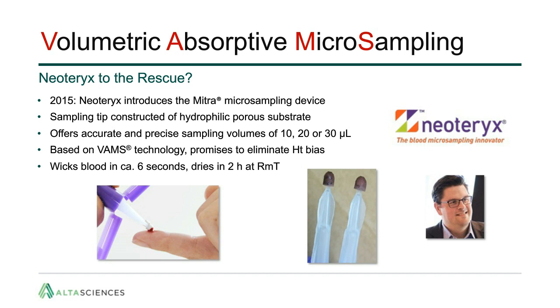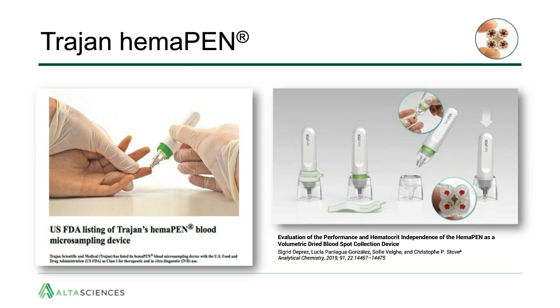Another volumetric approach is the Trajan hemaPEN, which received FDA approval as a Class 1 device on July 2nd for therapeutic and in vitro diagnostic use. It collects blood via four integrated 2.74 microliter microcapillaries, depositing blood on pre-cut paper discs when the cap is replaced. In our experience it was straightforward to implement, with the advantage of quadruplicate sampling for biobanking whilst eliminating tampering risk and maintaining sample integrity, with desiccant stored in the barrel of the pen.